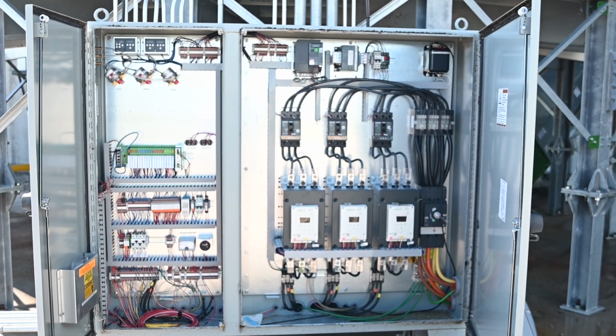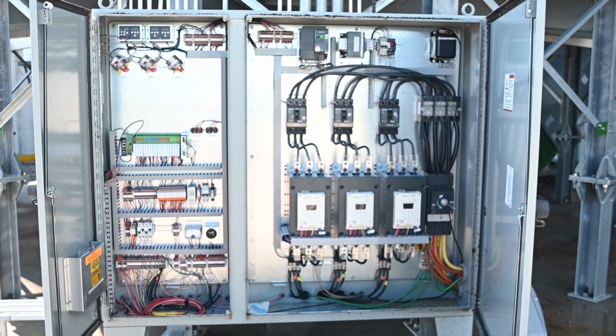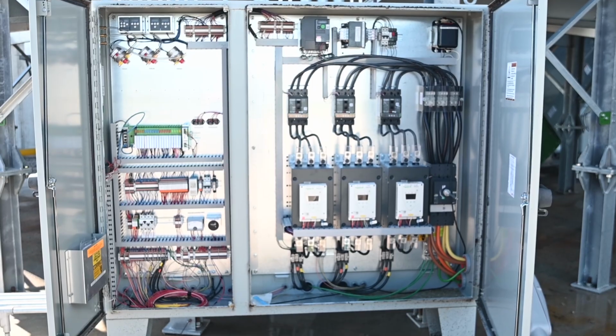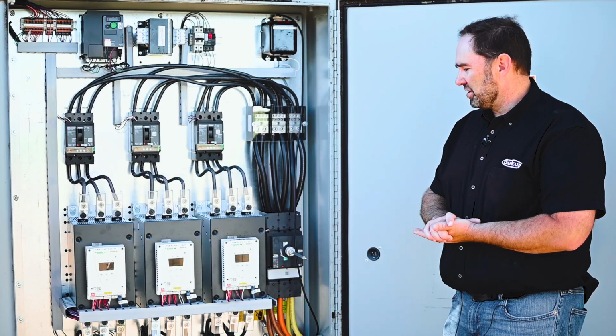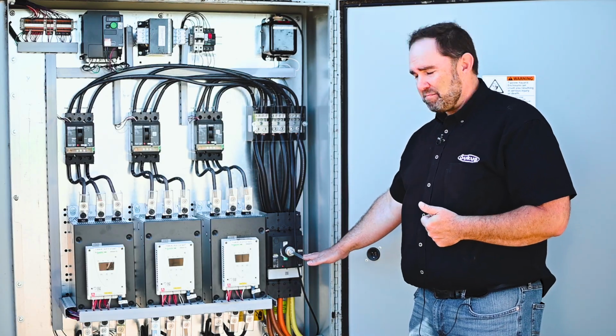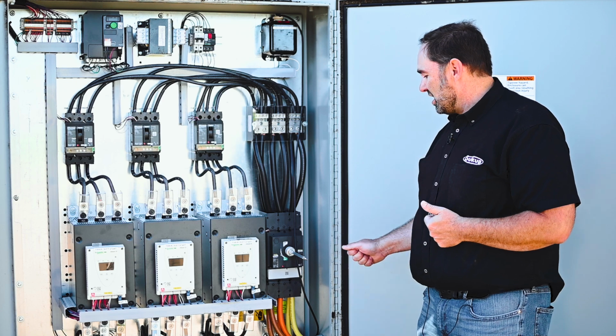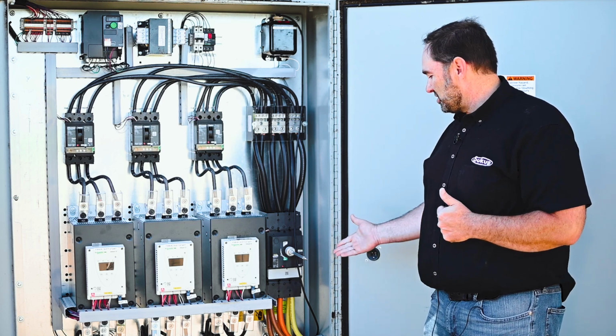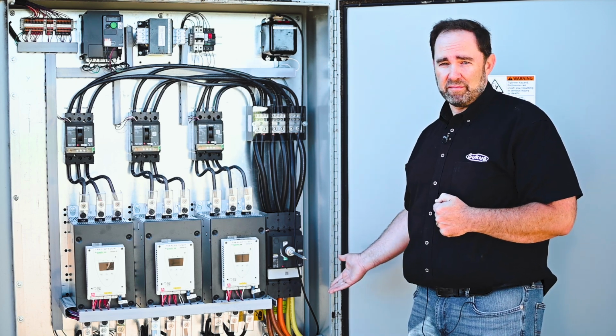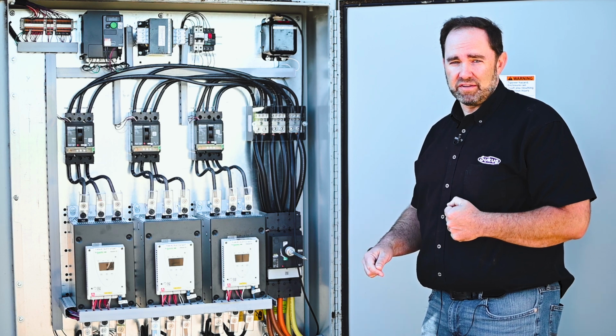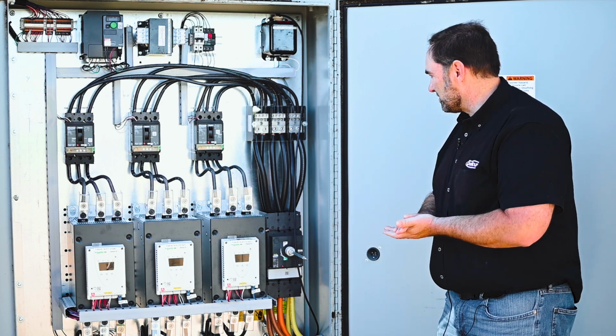So this is the right-hand side of the power cabinet, and this is going to be the high voltage, or the more dangerous side of the cabinet. So just to point out what the components are and what they do, we have a main switch, so all the main power will come into the bottom of that main switch. And keep in mind that even with the main switch off, you usually are going to have live power coming in the bottom unless it's been locked out coming into the dryer. So just be aware of that safety situation.